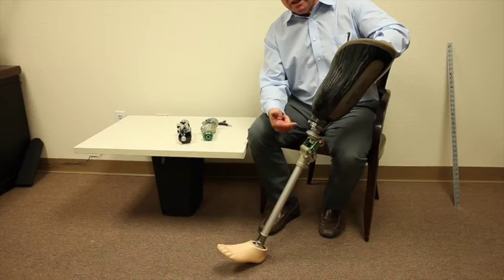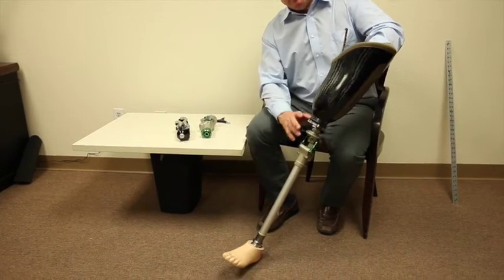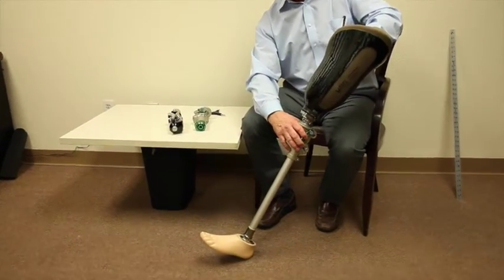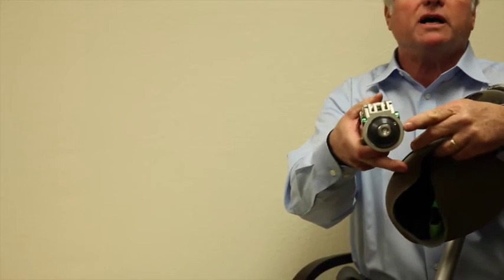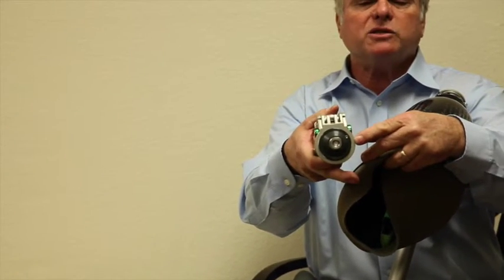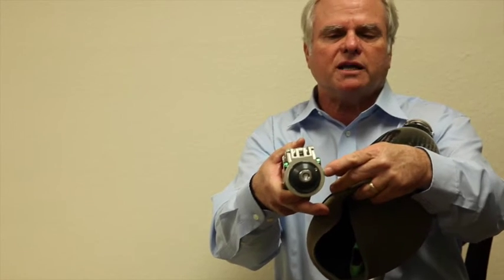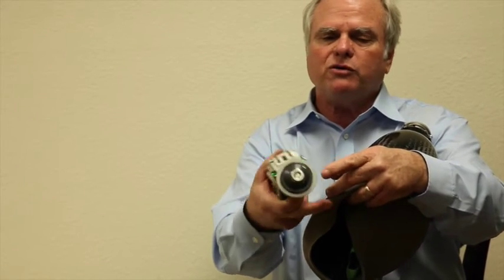Now this has the ability up on top, this pyramid will rotate so you can rotate the knee. There's a small screw, actually let me do this. There's a small screw right on top that when you get your rotation correct, two things you want to do.